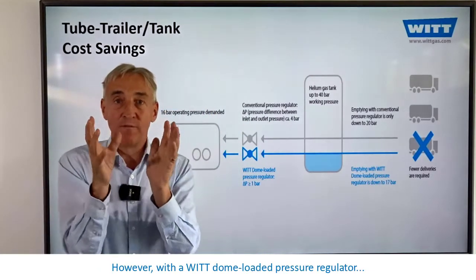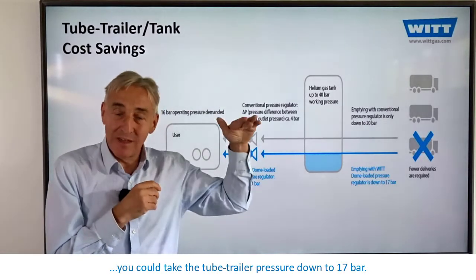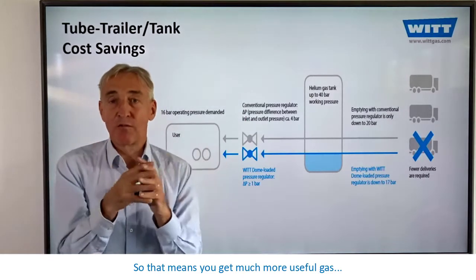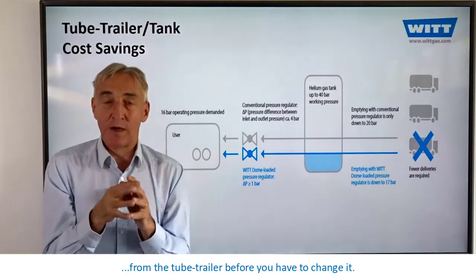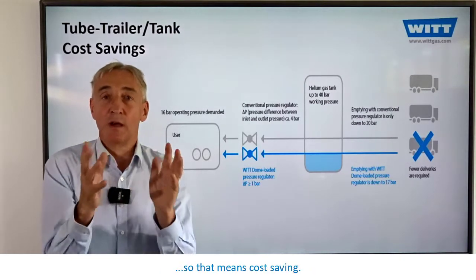However, with a WITT dome-loaded pressure regulator, you could take the tube trailer pressure down to 17 bar. That means you get much more useful gas from the tube trailer before you have to change it — so fewer deliveries, and therefore cost-savings.